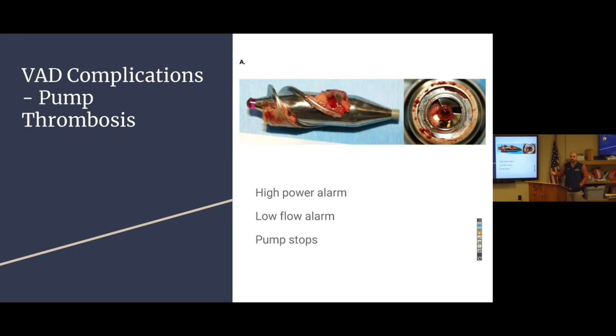Again, it's going to increase the amount of work the pump is doing, so you'll get a high power alarm. It's going to decrease the amount of flow through the pump, so you'll get a low flow alarm. Potentially the pump may stop - we'll talk about how you know if the pump has stopped.